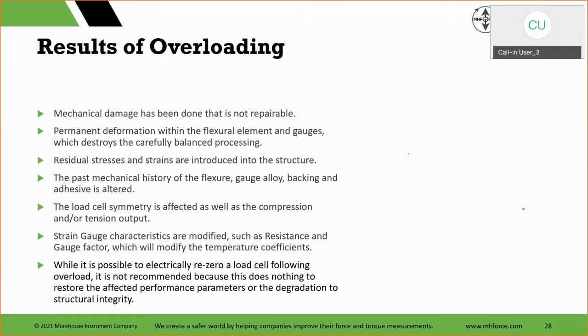That means, hey, maybe in compression now we're reading 10,100, and maybe in tension we were reading 9,900. And same with the millivolts. Maybe we're 3.9 and 4.1. That is a very good indication that someone overloaded the load cell if one mode goes high and the other mode goes low. That's where you want to check and make sure, use the load cell tester to check the zero balance. There's other meters that can do it if you're out there. Agilent 3458, Fluke 8508. There's a lot of other meters that can check the balance, but those are much more expensive than a load cell tester.